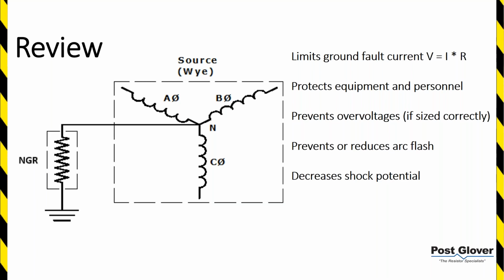And then for high resistance ground, it can prevent or reduce arc flash. By prevent, I mean on ground fault. Reduce could be, it heavily reduces at low voltage. That's to a lesser extent at medium voltage.